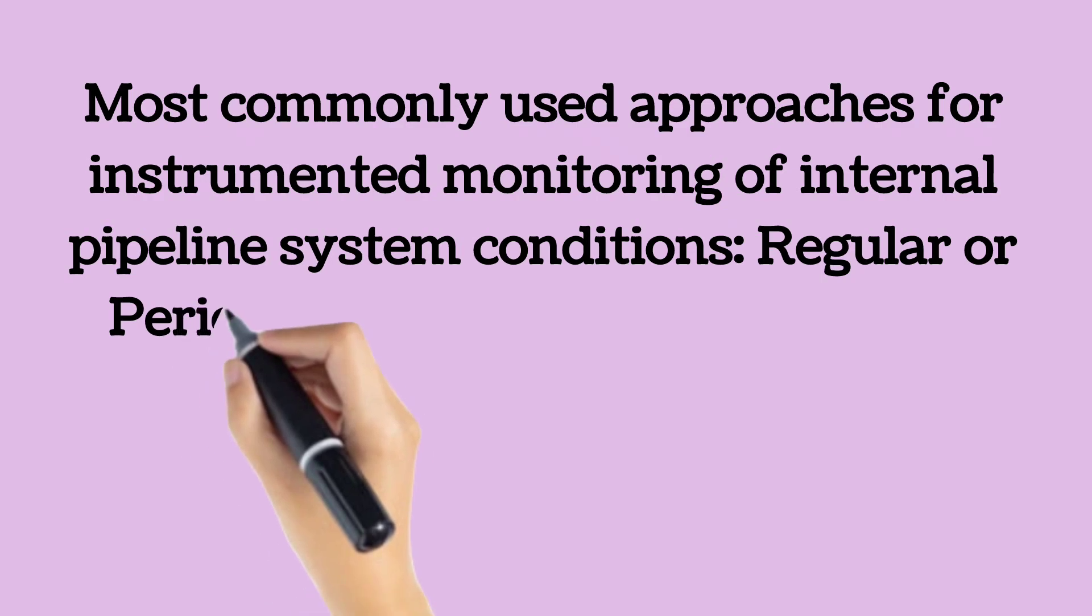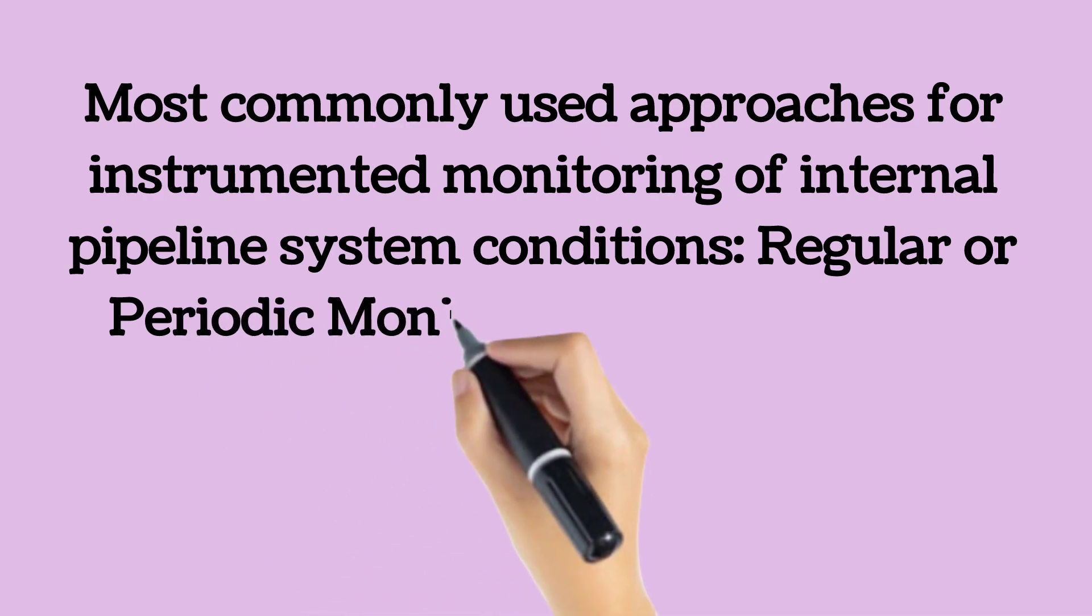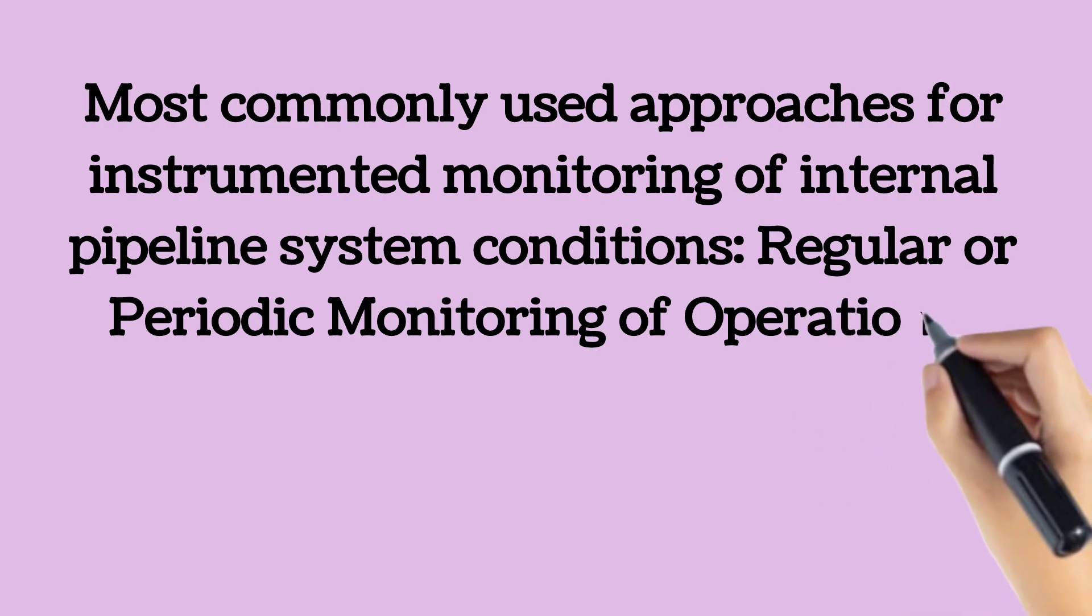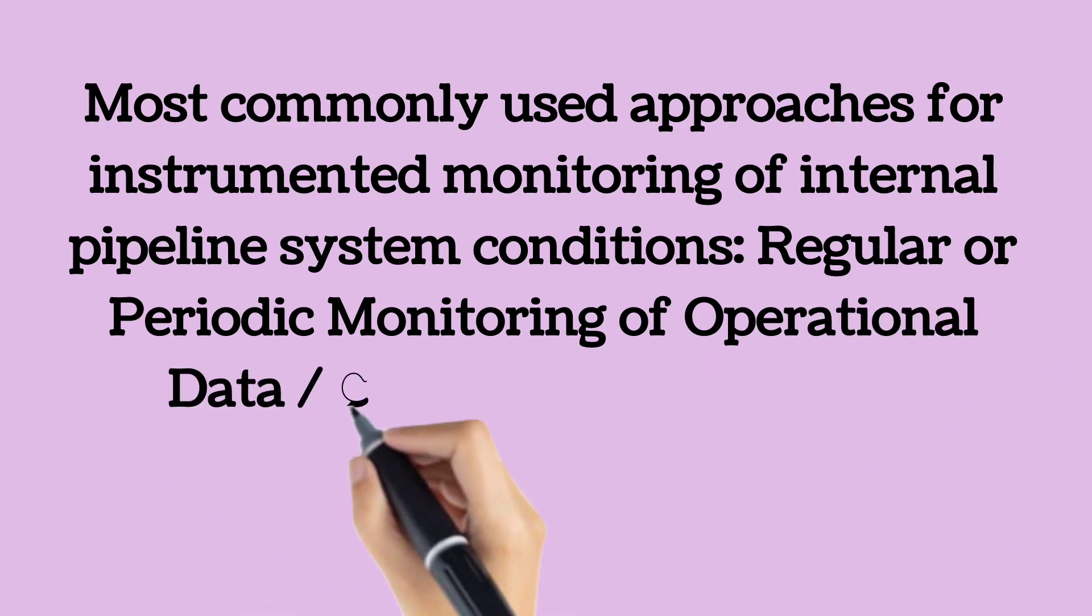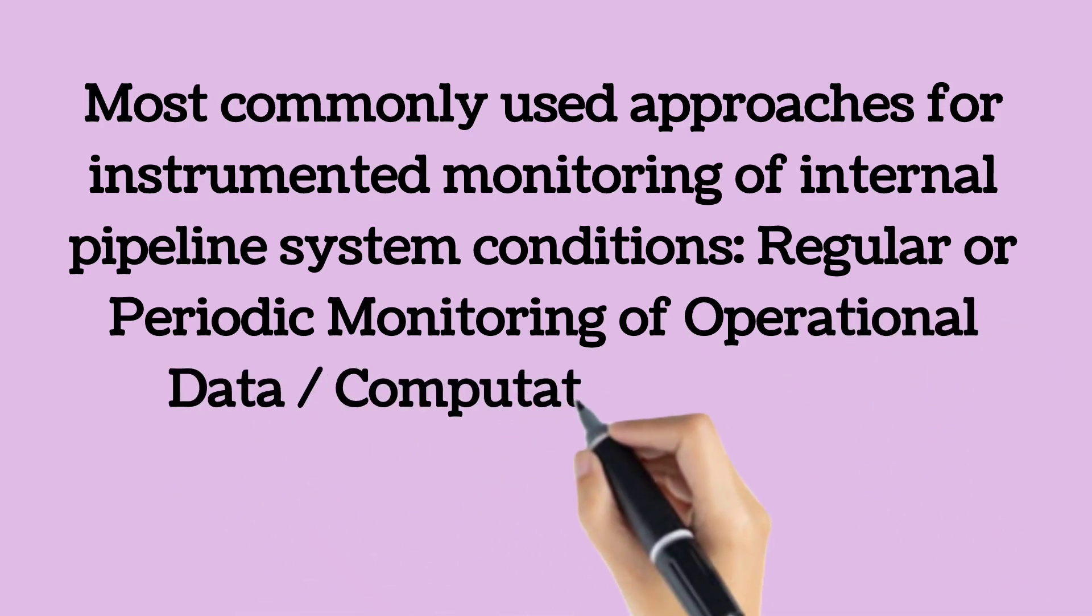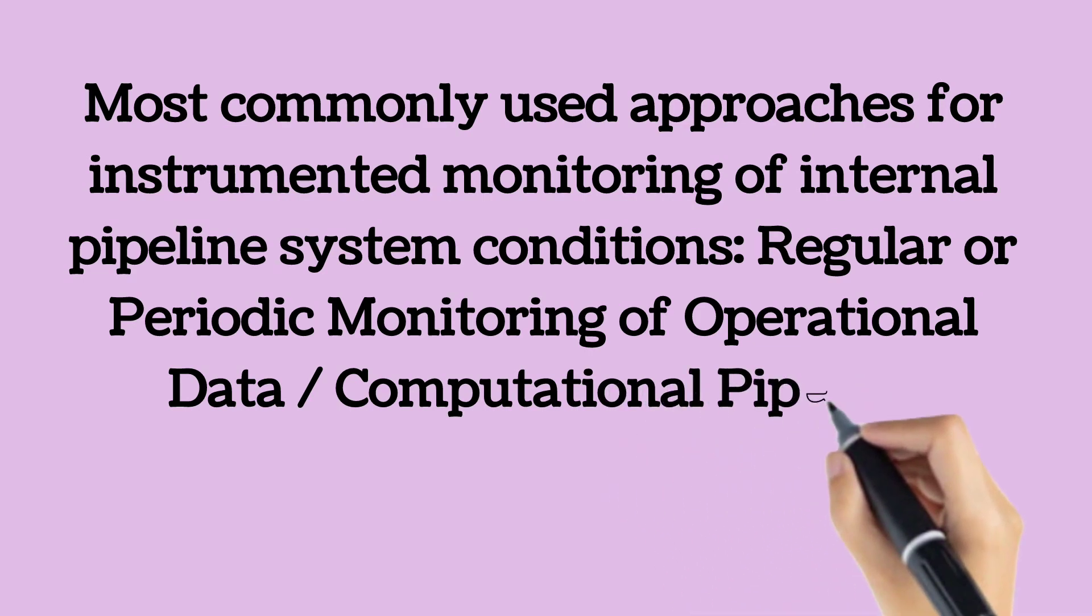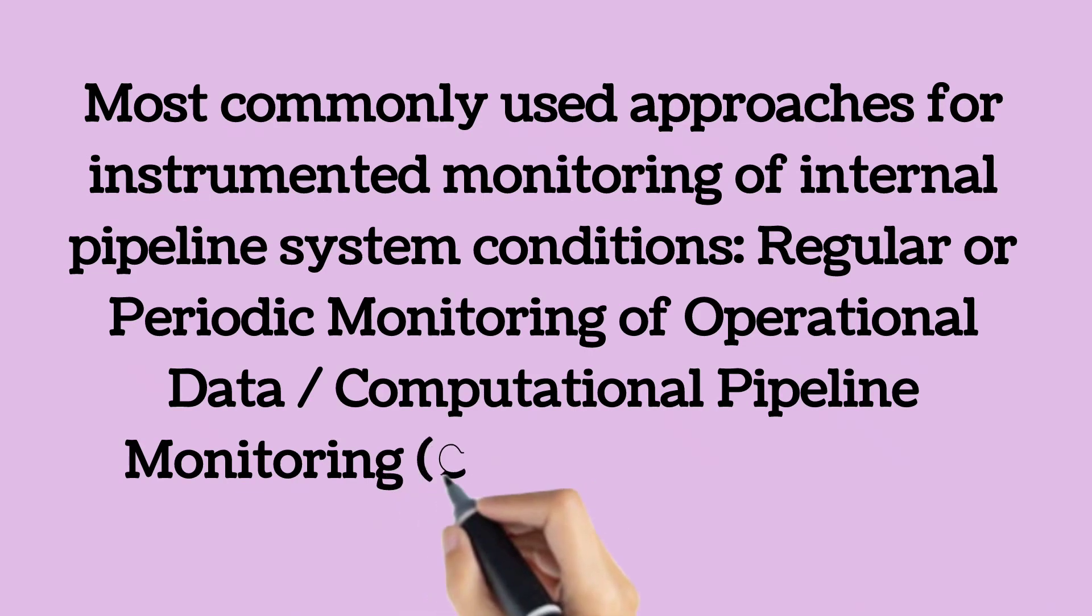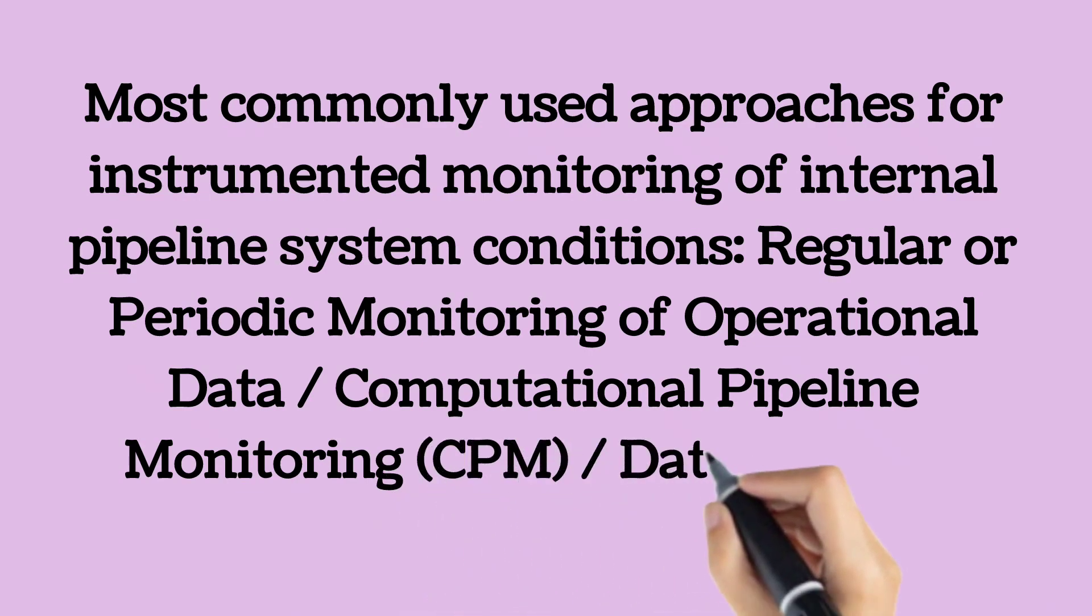For computational pipeline monitoring, CPM, the used approaches are mass balance with line pack correction and real-time transient modeling. Data modeling scenario are typically used. Data analysis methods include statistical methods and digital signal analysis for leak detection.